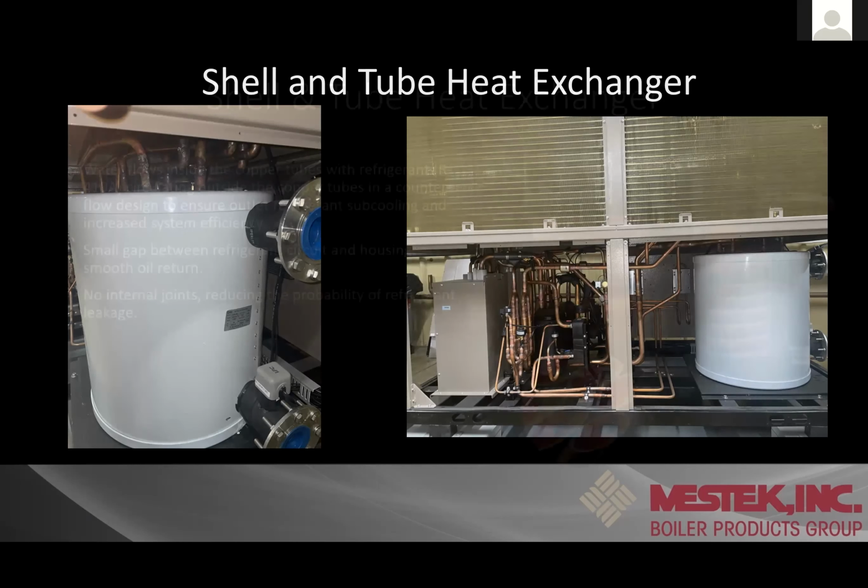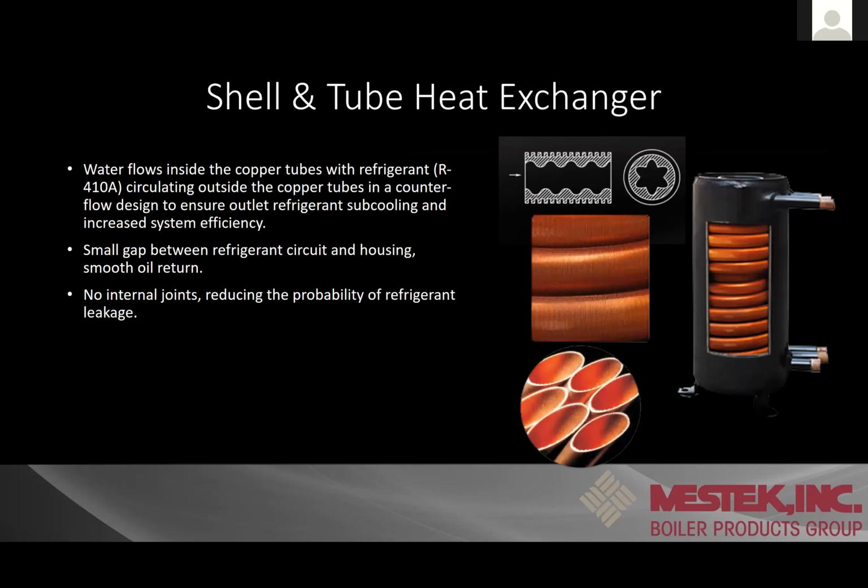So on the shell and tube heat exchanger, this is what they call a flooded evaporator coil. So this is where your phase changing is actually happening on the refrigerant, whether it's going from the liquid to a gas or a gas to a liquid. But on these tubes that you're looking at, you can kind of see the cutaway. The water flows through the inside of that tube, and your refrigerant phase changing is happening on the outside of that, so inside the shell.